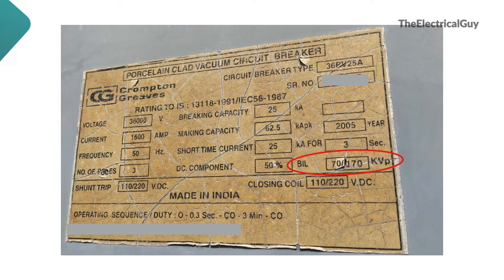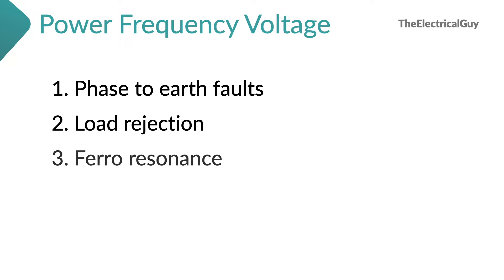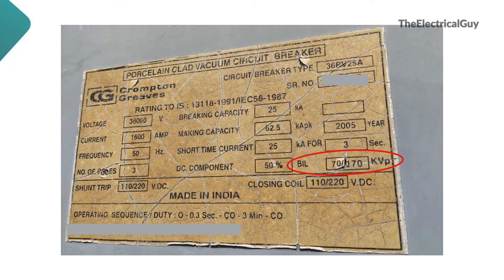Next is BIL or Basic Insulation Levels. The first value, 70 kV, represents the rated short-duration power frequency withstand voltage. Power frequency withstand voltage can be caused by phase-to-earth fault, load rejection, Ferro resonance, or the Ferranti effect. Hence, the breaker shall withstand power frequency voltage caused by these reasons. IEC has defined the level of power frequency voltage that can appear across the breaker contacts. The circuit breaker has to undergo a power frequency withstand test in which power frequency voltage is applied for 1 minute. So 70 kV represents that the breaker can withstand a power frequency voltage of 70 kV.